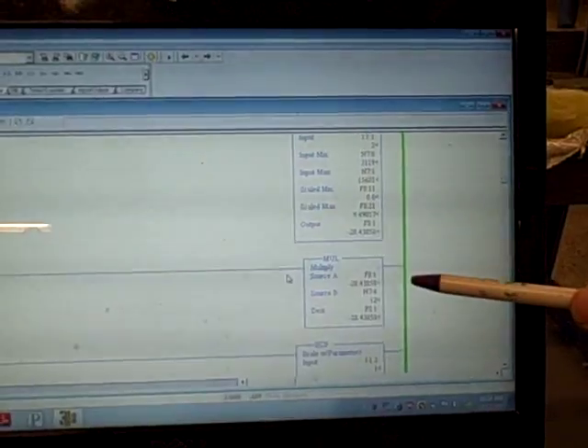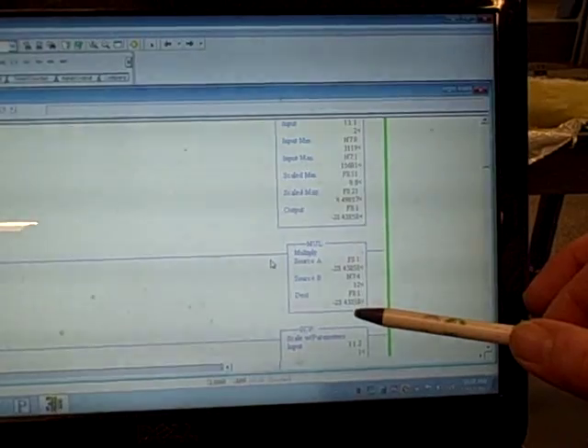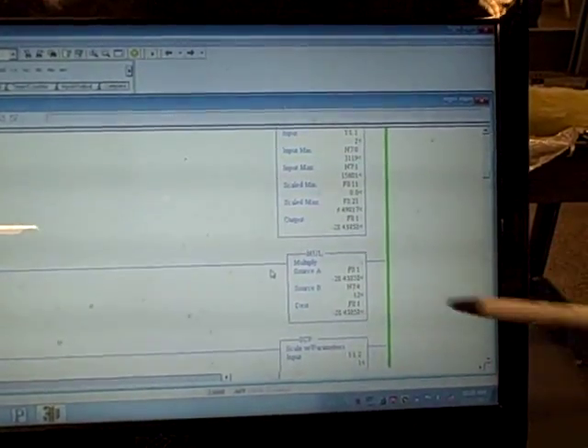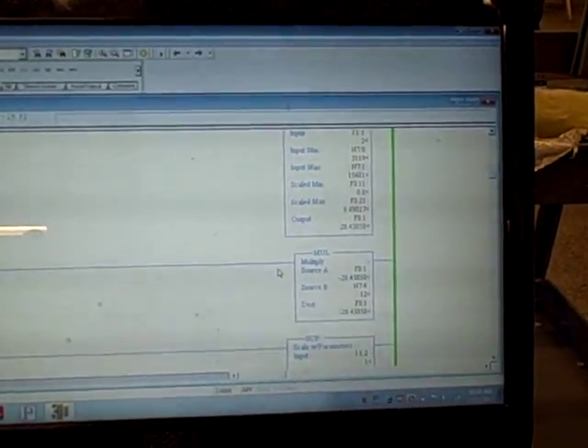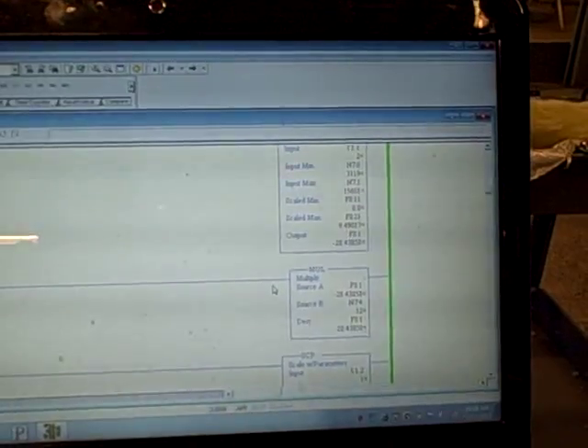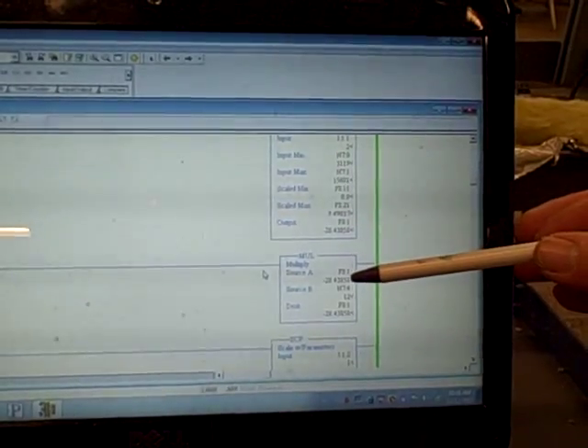It turns out this is actually doing what it should. The program is functioning the way it ought to: we take the value from F8:1, multiply it by 12, and stick that value back into F8:1. The actual product is minus 28.4. So why do we see the same minus 28.4 both before and after the multiply? Shouldn't the first be smaller and the second be larger? Well, this is a very important lesson when using live displays on a running PLC — what you see on the screen is not necessarily what is happening in the order of operations in the program. The real value of F8:1 after the SCP instruction is a little greater than negative 2, and that's what you should see there. Then it gets multiplied by 12 and you should see minus 28.4 after that.